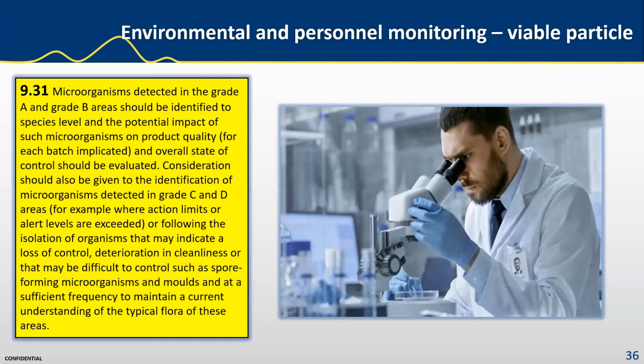And once you compile this data in a central contamination control strategy database, it will be easier to track such issues in real time and make faster responses to tackle the issues. Some companies take months to figure out their rise in fungi within their clean room, and it's down to cleaning agents not being rotated because this was not recorded or monitored. In fact, the issues came from the grade D environment and were transported into a grade A one where they showed up, and so the root cause investigation was focused in the grade A environment instead of where the contamination came from. And this is where we're headed, folks, and I believe digital technology and digital data transfers are the future of clean rooms in general.